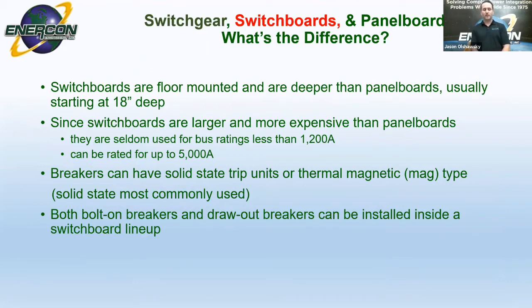Switchboards are floor mounted, similar to switchgear, but they are deeper than panel boards, usually starting at 18 inches deep. Since switchboards are larger and more expensive than panel boards, they are seldom used for bus ratings less than 1200 amps. So they can be up to 5000 amps. So if you were in a lower amperage there, you would probably go with the panel board in place of a switchboard. But as you get larger in size of your loads there, you're going to need that extra copper bus and space there. So you'd go with a switchboard.